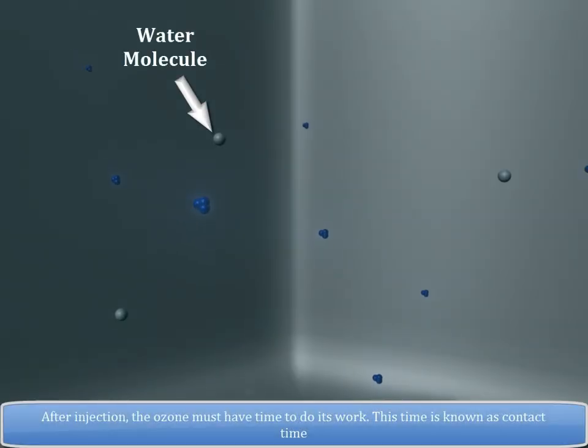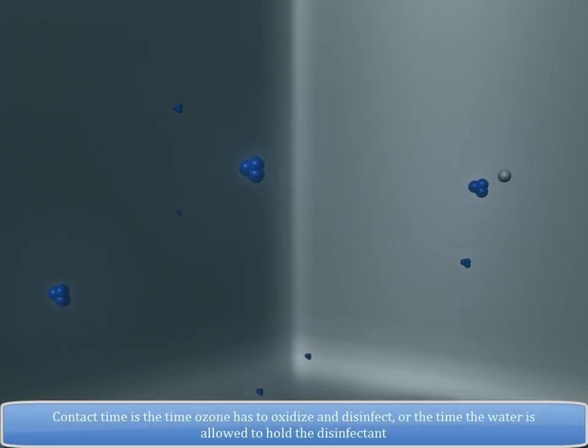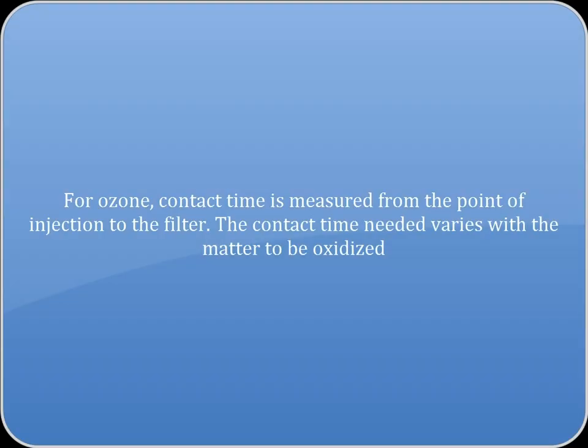After injection, the ozone must have time to do its work. This time is known as contact time. Contact time is the time ozone has to oxidize and disinfect or the time the water is allowed to hold the disinfectant. For ozone, contact time is measured from the point of injection to the filter.